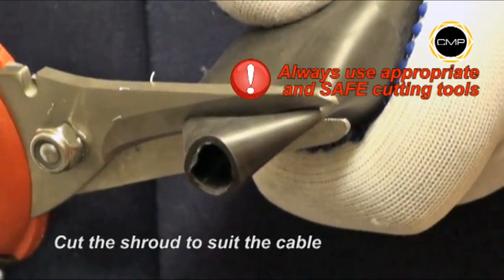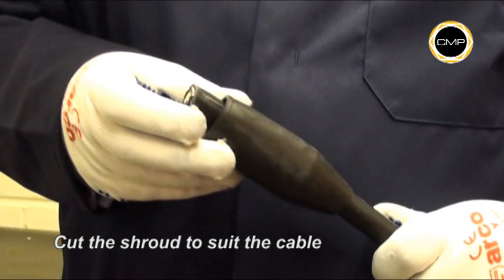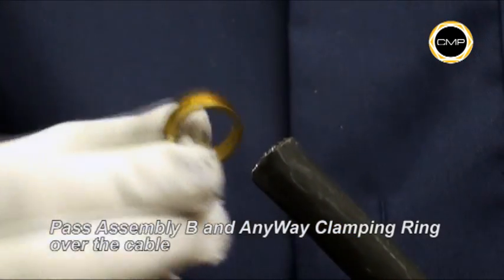If required, cut the shroud to suit the cable diameter, then pass the shroud over the outer sheath. Pass Assembly B, outer seal nut first, over the cable, followed by the AnyWay Clamping Ring.